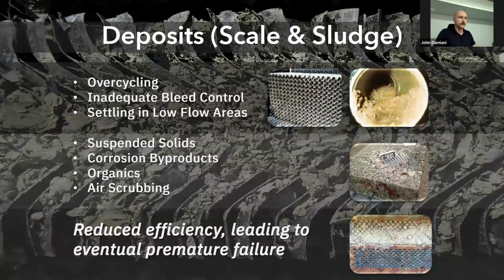Heat exchangers, the same thing. So this can occur due to overcycling. We'll talk about cycles of concentration a little bit later, just to make sure everybody understands all the terminology. It can occur due to inadequate bleed control, which is part of overcycling. But the bleed from your system, the automatic draining of water from the system, also helps clear sludge out of the system. So it removes some of the suspended solids as well, which can cause fouling. And then you also have low flow areas in the system, which can cause settling.